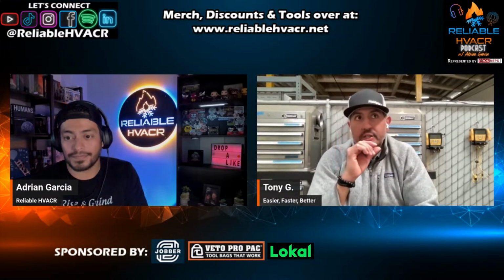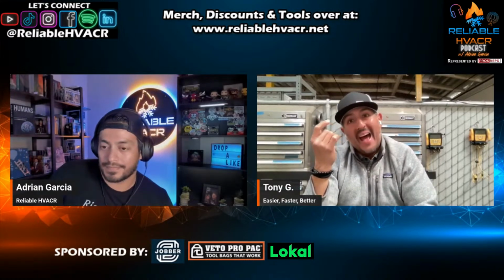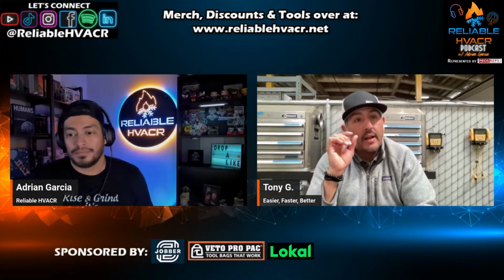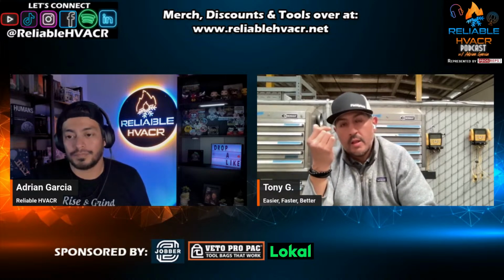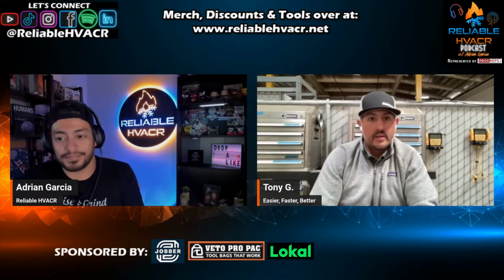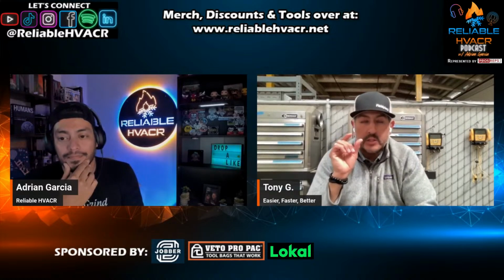Now, the primary function of a valve core removal tool is to remove the valve core. Now, I would say in the past 10 years or so plus, the industry has recognized a secondary benefit of removing the valve core from the service valve. What's that benefit? We all got to put them on when we vacuum. Yes, right?